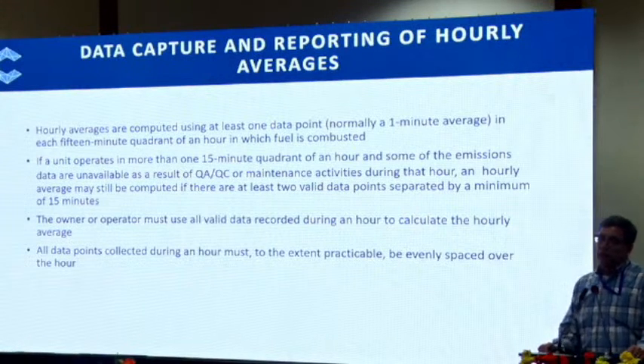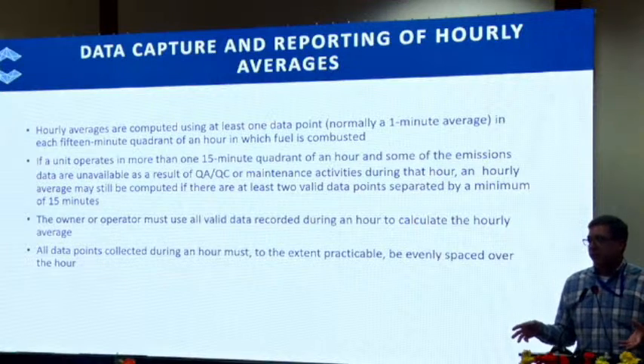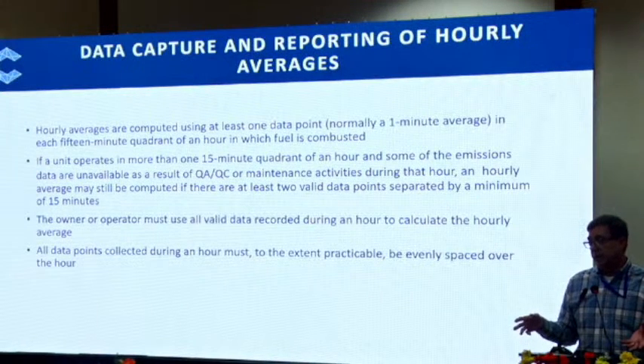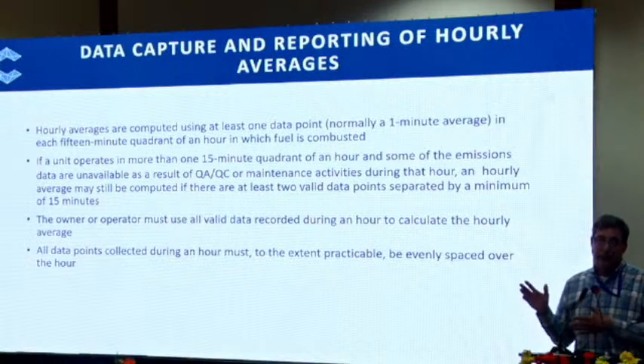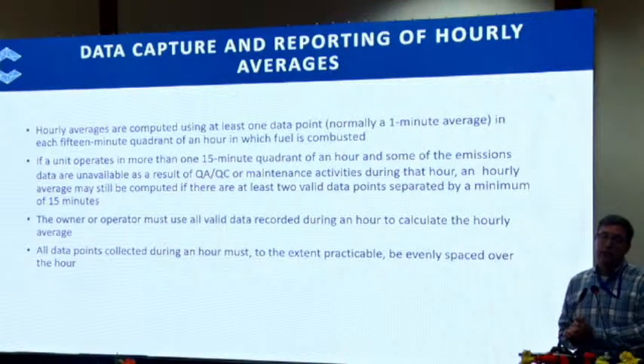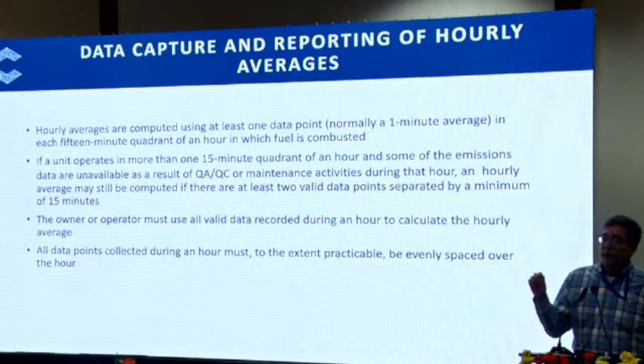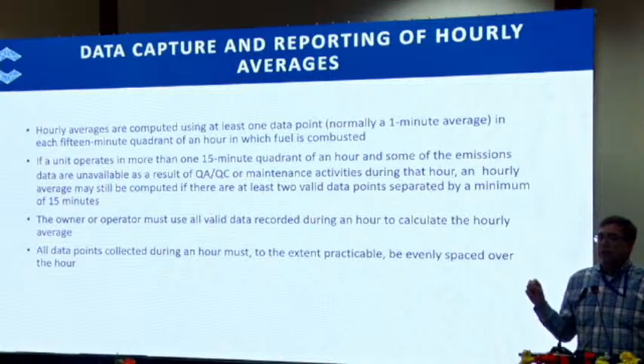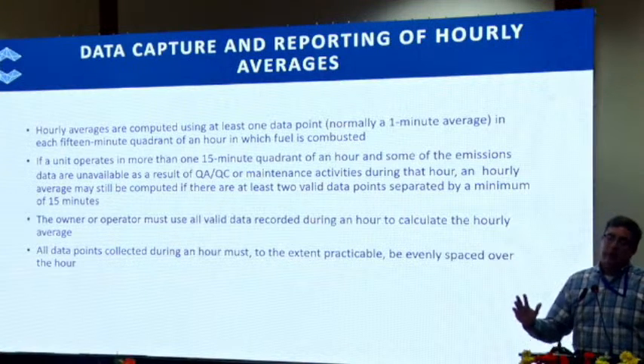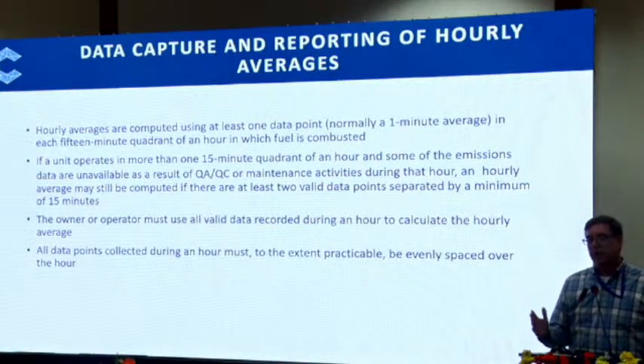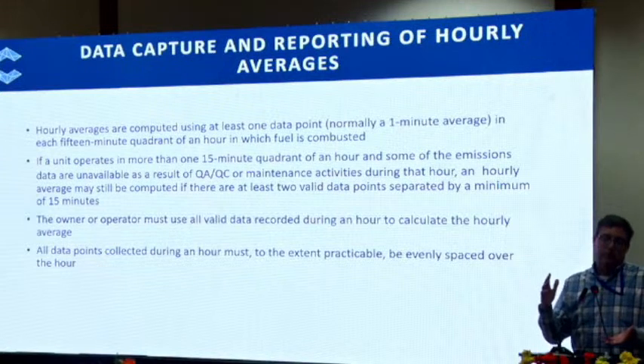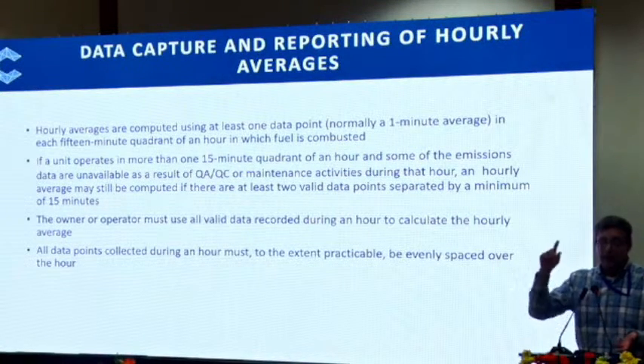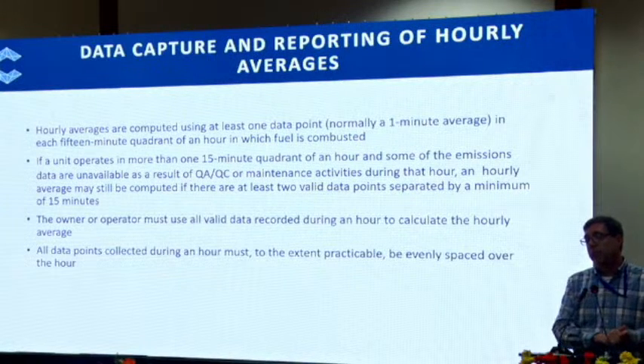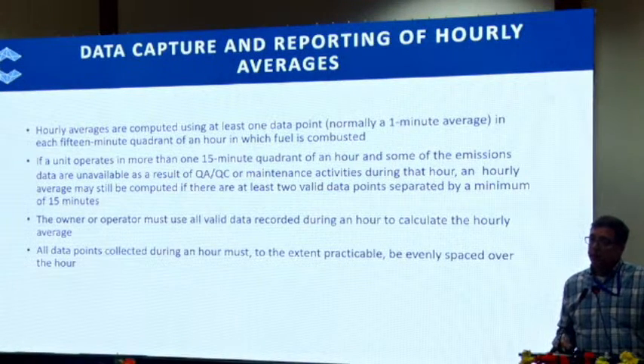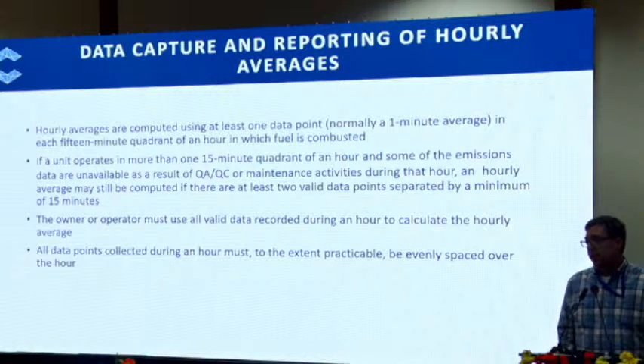So this is a little interesting because we have to be careful for data availability. We have very high data capture rates, but the reason we do is because we have our technicians who maintain our equipment watch the clock. So they would conduct a linearity. They would do the first set of injections. They would start after the top of the hour, so they have their first minute, and say it takes them 30 minutes to do the 3 injections, and they could capture 1 other minute in the last 15 minutes. That gives them a valid hour. They can proceed into the next hour.